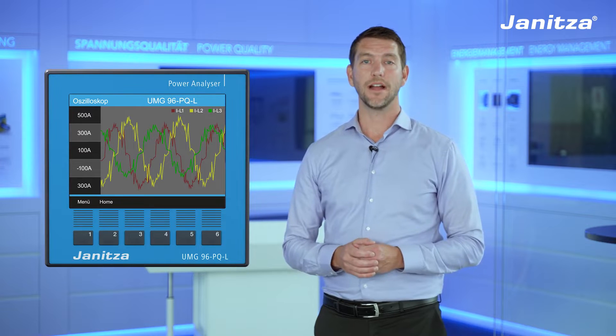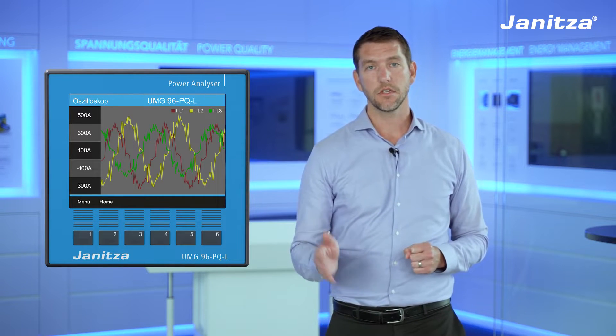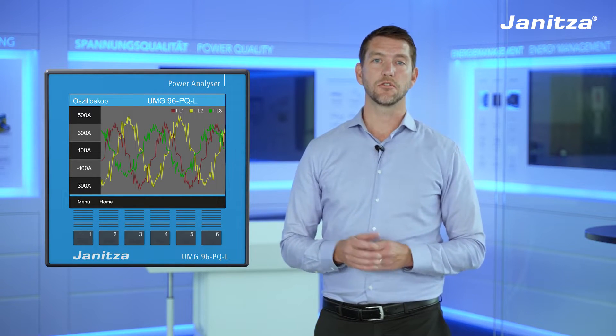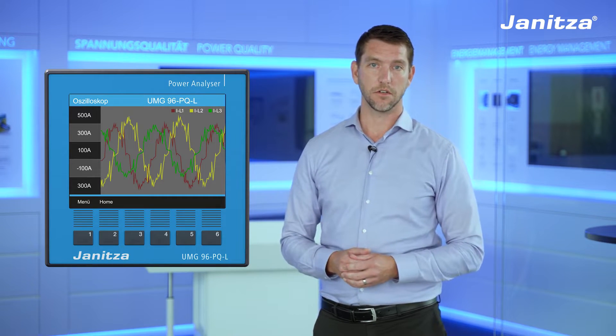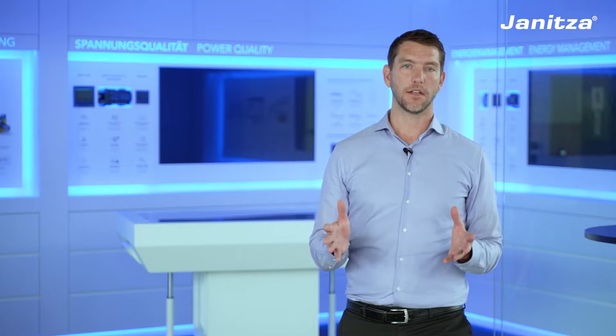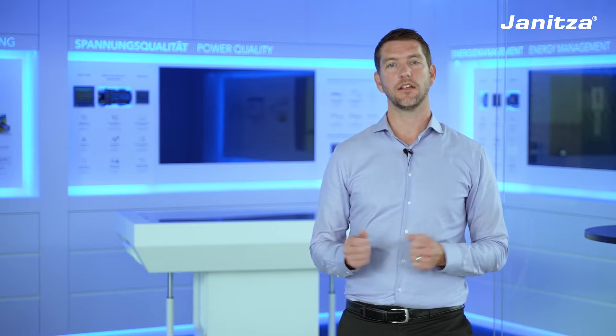This is a device that will monitor your power distribution and sub-distribution, and ensure transparency in your power quality and residual current monitoring. Nowadays, production plants are equipped with tons of active infeed power electronics and nonlinear loads. Power electronics generate harmonics, transformer saturations, equalization, and vagabonding currents.